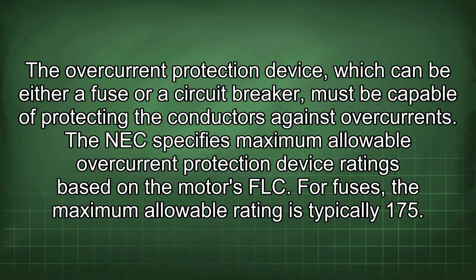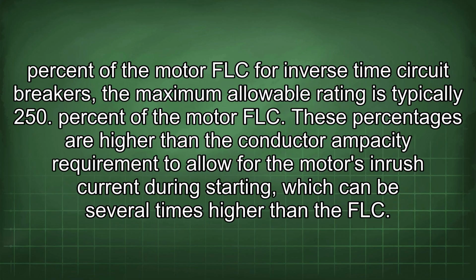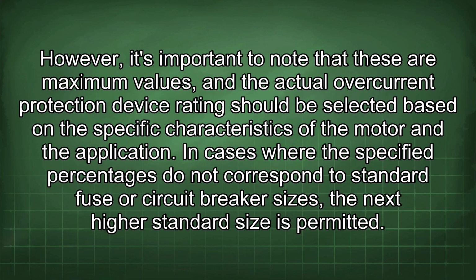The NEC specifies maximum allowable overcurrent protection device ratings based on the motor's FLC. For fuses, the maximum allowable rating is typically 175% of the motor FLC. For inverse time circuit breakers, the maximum allowable rating is typically 250% of the motor FLC. These percentages are higher than the conductor ampacity requirement to allow for the motor's inrush current during starting, which can be several times higher than the FLC. However, it's important to note that these are maximum values, and the actual overcurrent protection device rating should be selected based on the specific characteristics of the motor and the application. In cases where the specified percentages do not correspond to standard fuse or circuit breaker sizes, the next higher standard size is permitted.